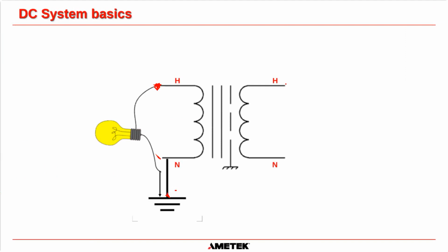As an example, you can connect a lamp directly between the hot and any part of the ground circuit on the primary, and you can attach a light bulb or a lamp, and that lamp will light. I'm not connecting it between hot and neutral. I'm connecting it between hot and ground. That lamp will light because neutral is the same point as ground. Okay?